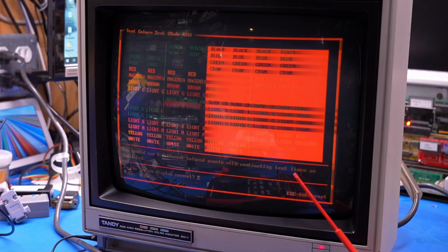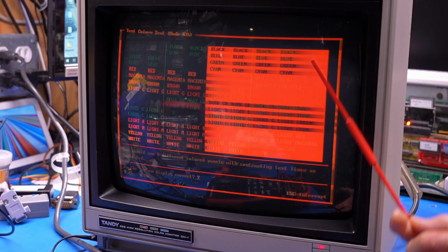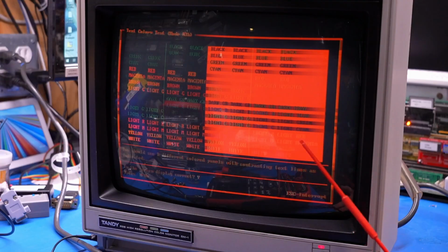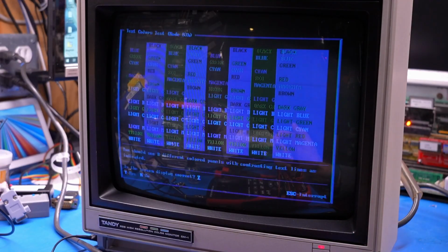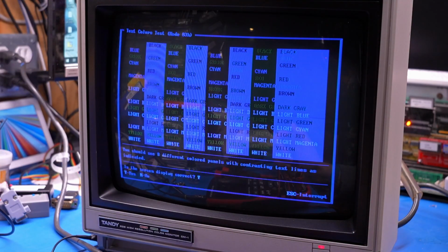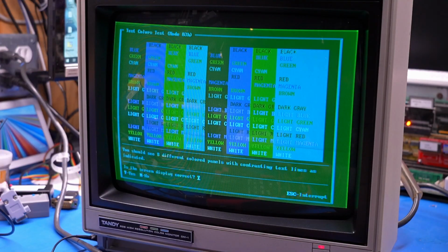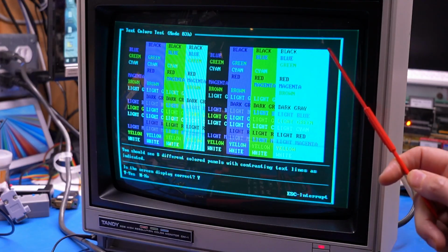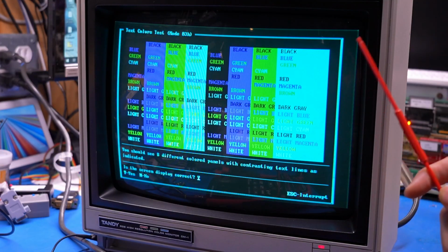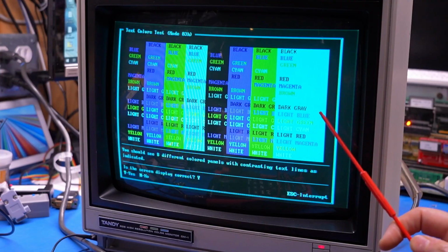And what you could see looking at the screen here, when we're looking at just the red turned up and the other two turned down, is that all the smearing that we were seeing, which I initially was thinking was actually something to do with the blue and the green circuit, has nothing to do with those. It's entirely to do with the red cathode drive. In fact, what I'm doing now is I am turning the green and the blue back up again. And now when you look at the image, there's absolutely no smearing whatsoever.